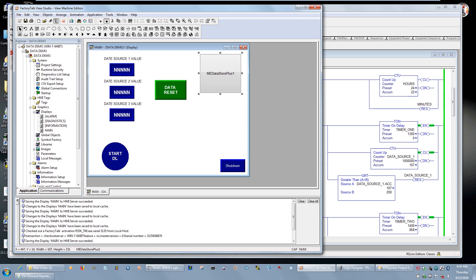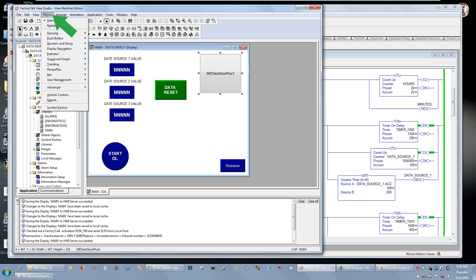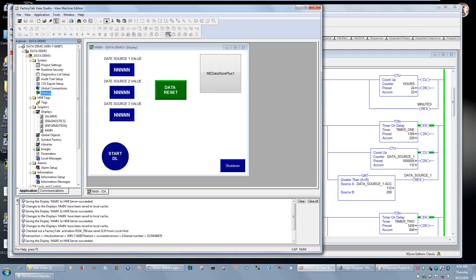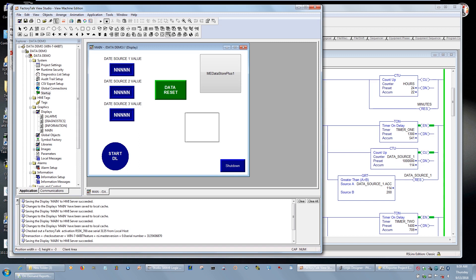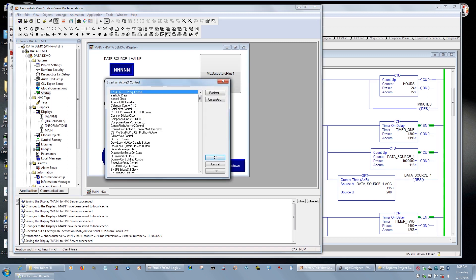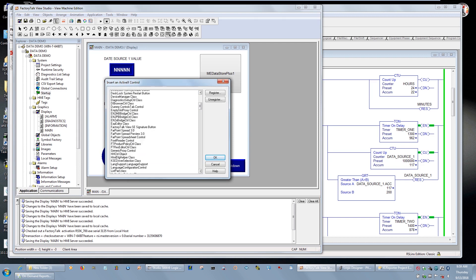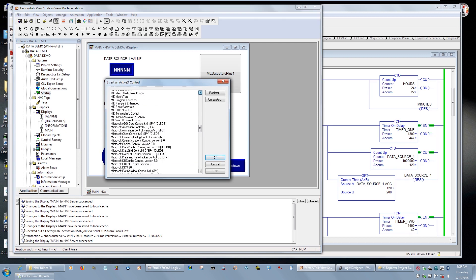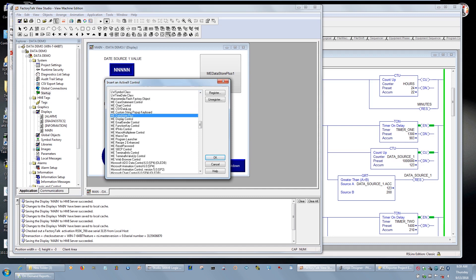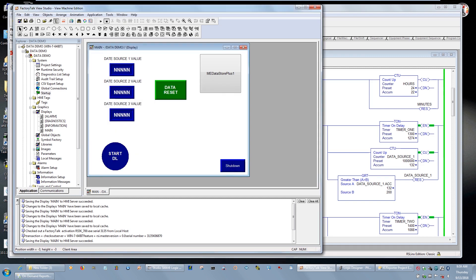To add it, go to Objects, then ActiveX Control. As with most objects, you have to draw it. When you let go, you'll see all the available choices. If you scroll down to midpoint, you'll see items beginning with 'ME' — those are Machine Edition features that run on a PanelView Plus. Specifically, we're looking at the ME Datastore Plus object to do data logging to a CSV file. I'll hit Cancel because I already set this up, but I just wanted to show you where it's located.